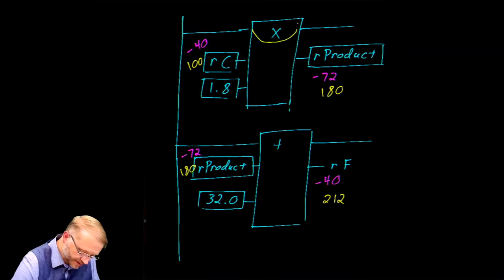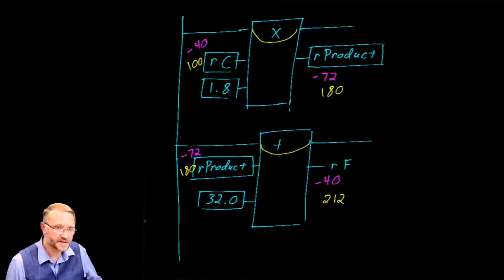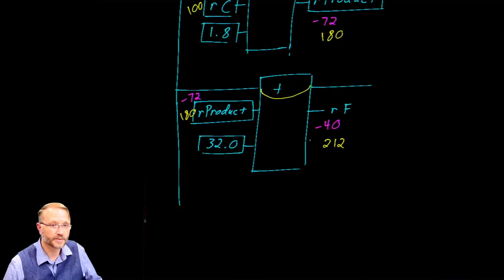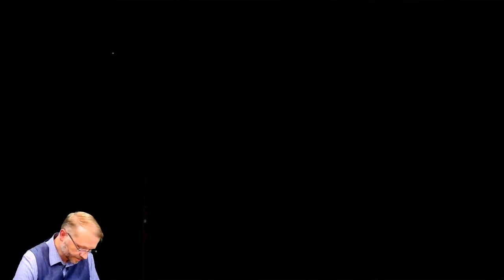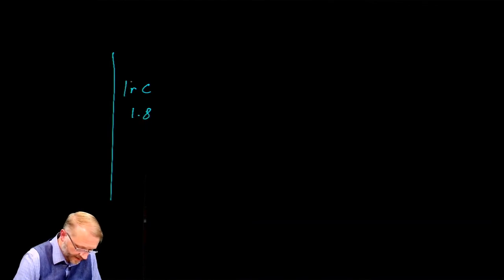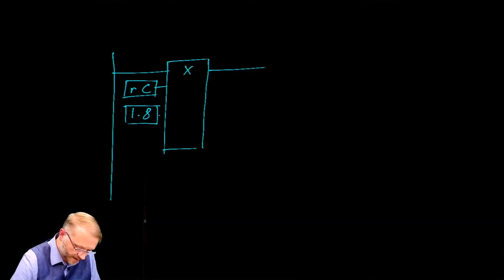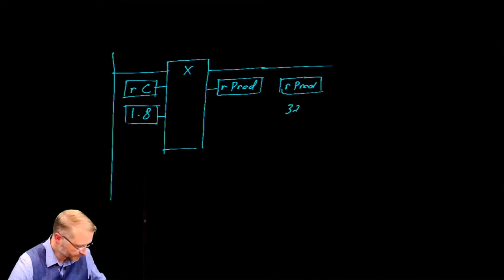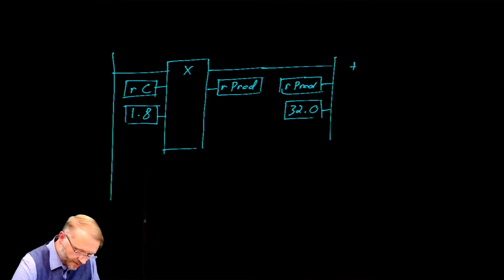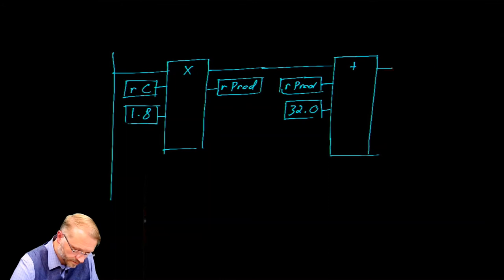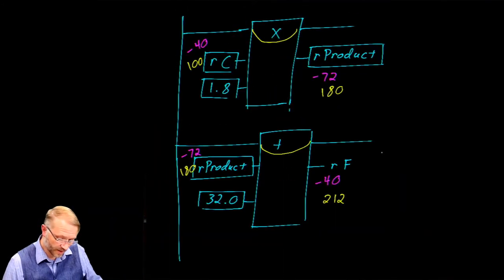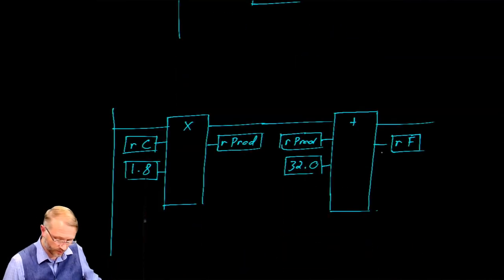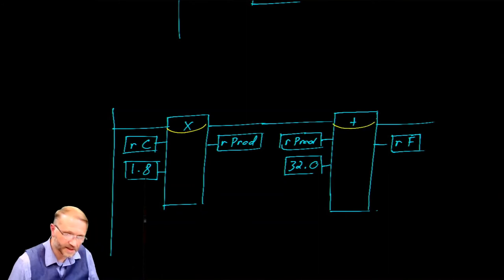These multiplier and adder blocks are internally connected to each other, which suggests there might be a cleaner way to draw this code — you could put everything on a single rung. The first part looks the same: Celsius and 1.8 through a multiplier, output goes to product. We then take real product and 32.0 through an adder, giving us real Fahrenheit. Same operation, except now everything's on a single rung, and that works because our enable out is a copy of enable in.